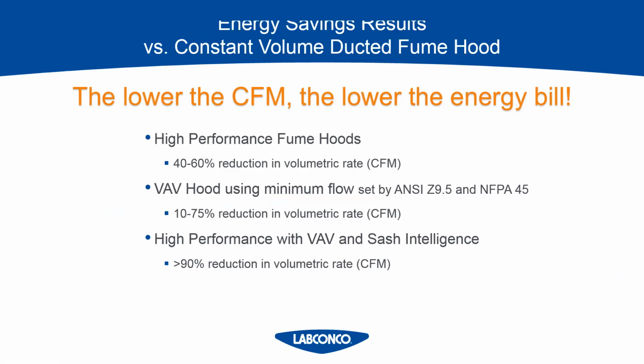Using a variable air volume hood, or a VAV hood, where the amount of air that's being exhausted changes as the sash goes up and down, you can lower your air consumption by 10 to 75%. And you're probably looking at this going, wow, that's a really big range, 10 to 75%. Because in order to be effective, the sash has to be lowered on a VAV system. If it's never closed, then you never see a change in air being exhausted. So it would act just like a constant volume hood if you never change the sash position.